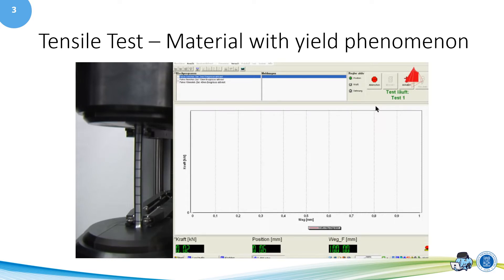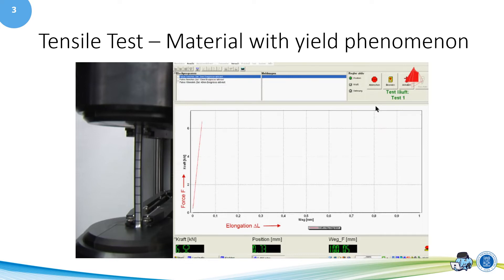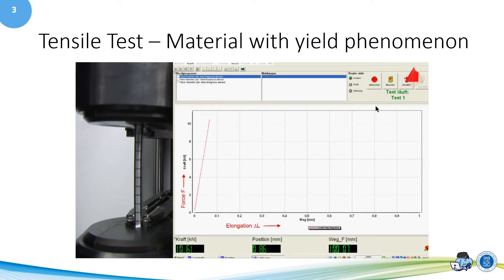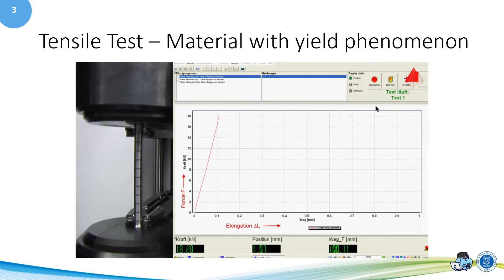During the tensile test, the test piece is slowly and constantly elongated with a standardised speed. The force that the test piece opposes to the imposed elongation is recorded and can be seen at the bottom left-hand corner of the computer display. The material behaviour can best be observed in a force-elongation diagram. The force F is plotted upwards on the vertical axis, the elongation delta L towards the right on the horizontal axis. At first, the force rises rapidly. Force and elongation are proportional and form a steep, straight line in the diagram. In this area, the material behaves elastically. If the test piece were to be unloaded from this area, it would spring back completely to its original length.